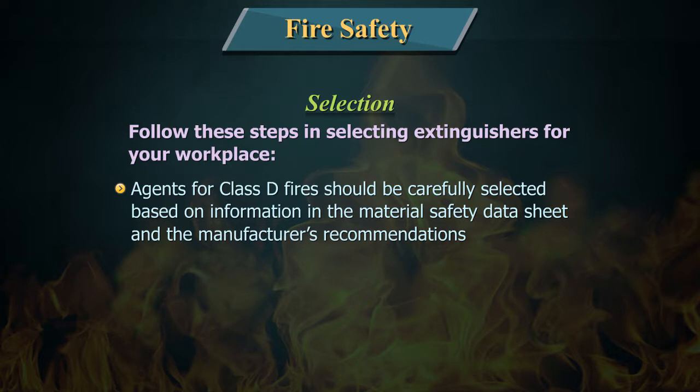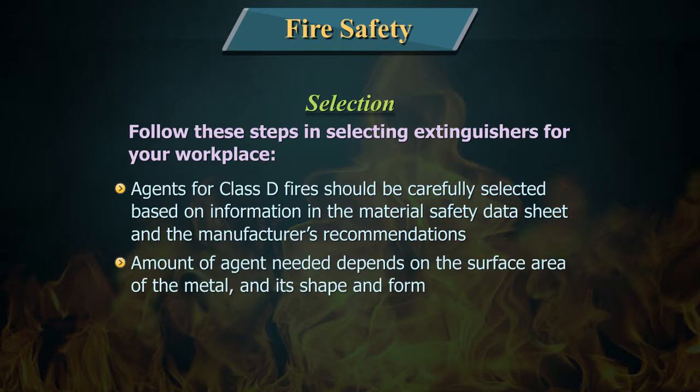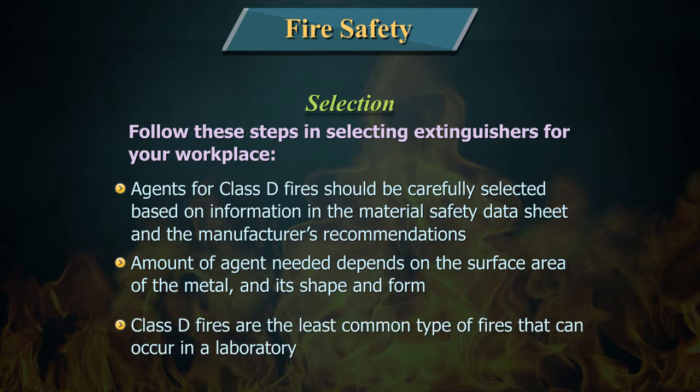Agents for Class D fires should be carefully selected based on information in the material safety data sheet and the manufacturer's recommendations. The amount of agent needed depends on the surface area of the metal and its shape and form. Class D fires are the least common type of fires that can occur in a laboratory.